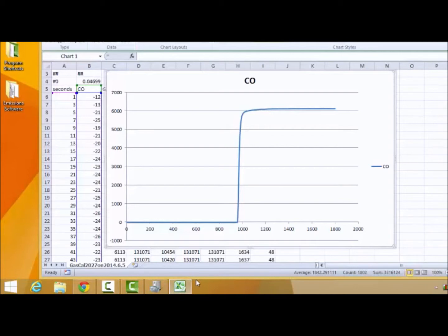Next, let's go over processing this calibration data. Once you've recorded the calibration data into a CSV file, it will need to be processed before it can be entered into the sensor box. The calibration procedure exposed the CO sensor first to a 0 carbon monoxide environment for several minutes, followed by a known concentration of 300 parts per million for several more minutes. However, the output from the sensor is in log units. As you can see in this graph, it goes from 0 to 6,000. We need to map this into a range of 0 to 300 ppm.